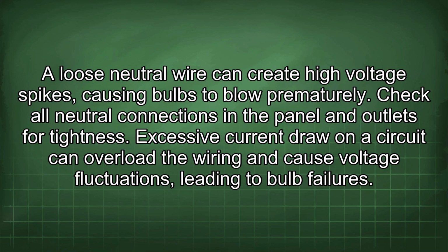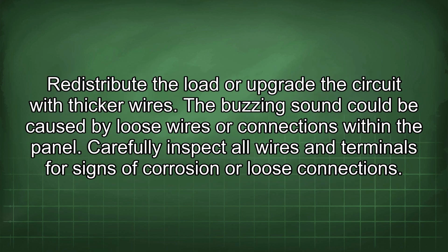Excessive current draw on the circuit can overload the wiring and cause voltage fluctuations, leading to bulb failures. Redistribute the load or upgrade the circuit with thicker wires. The buzzing sound could be caused by loose wires or connections within the panel. Carefully inspect all wires and terminals for signs of corrosion or loose connections.